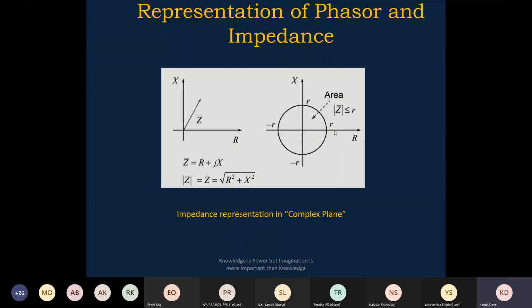Normally the backup impedance function and source kind of function are used to understand whether the backup fault is there and how the relay is detecting those kinds of things. Some manufacturers follow the non-directional impedance function, like MiCOM relays. Some manufacturers use the non-directional impedance but with polygon characteristics, not circle characteristics. MiCOM uses the circle characteristics like this, whereas Siprotec uses the polygon characteristics, and ABB gives the unidirectional circle characteristics, which is called Mho characteristics or offset Mho characteristics. So it has to be understood properly how the Z function works.